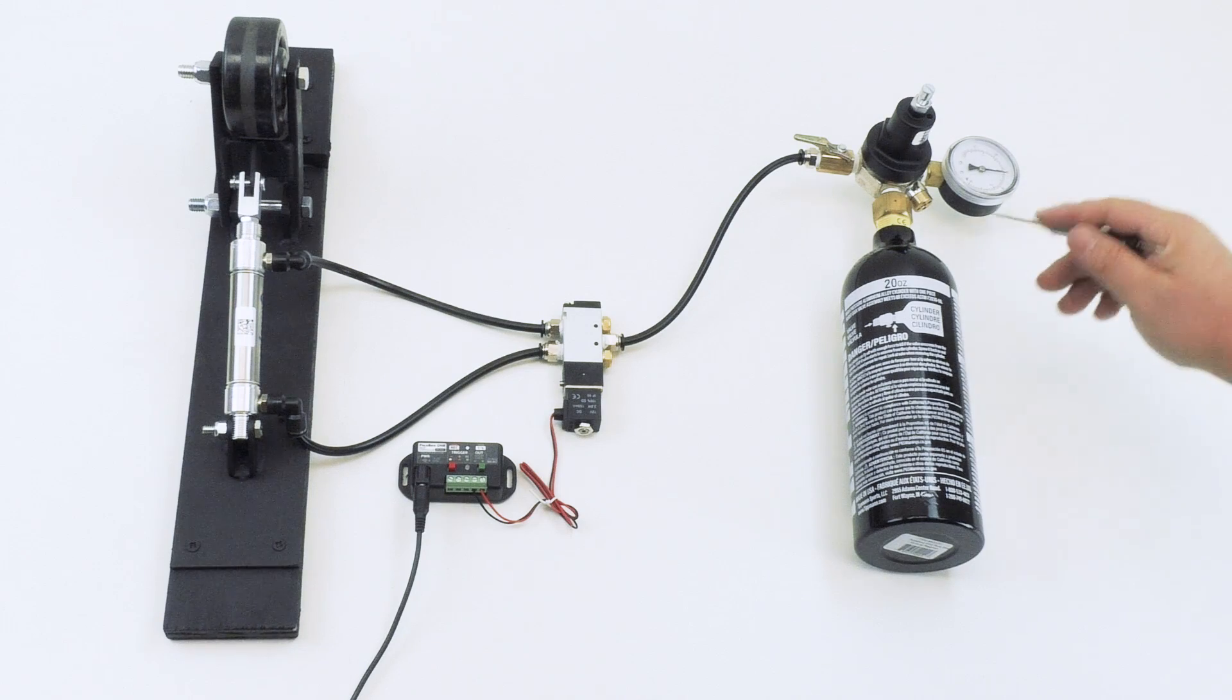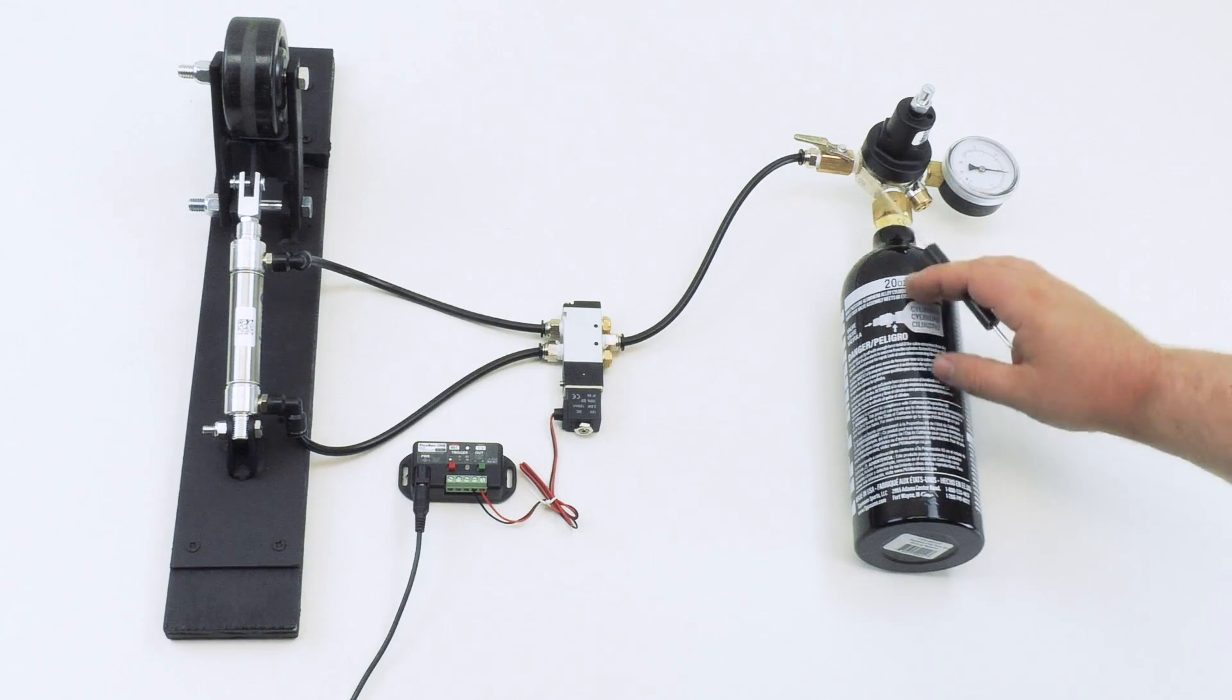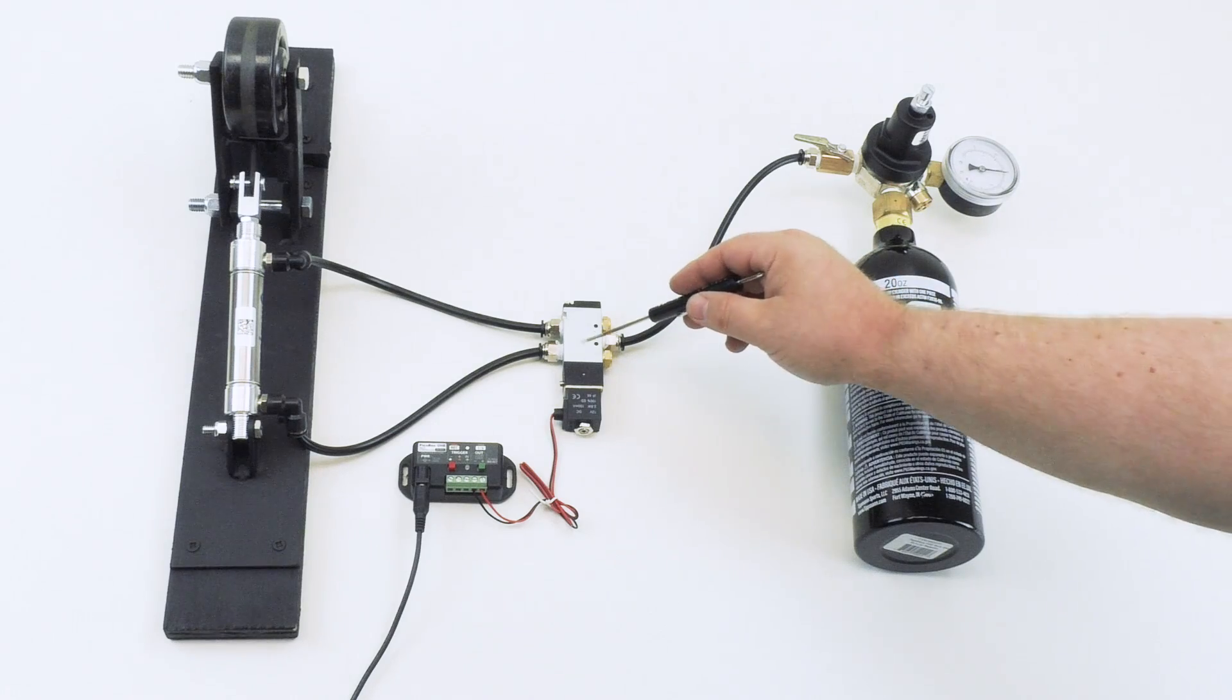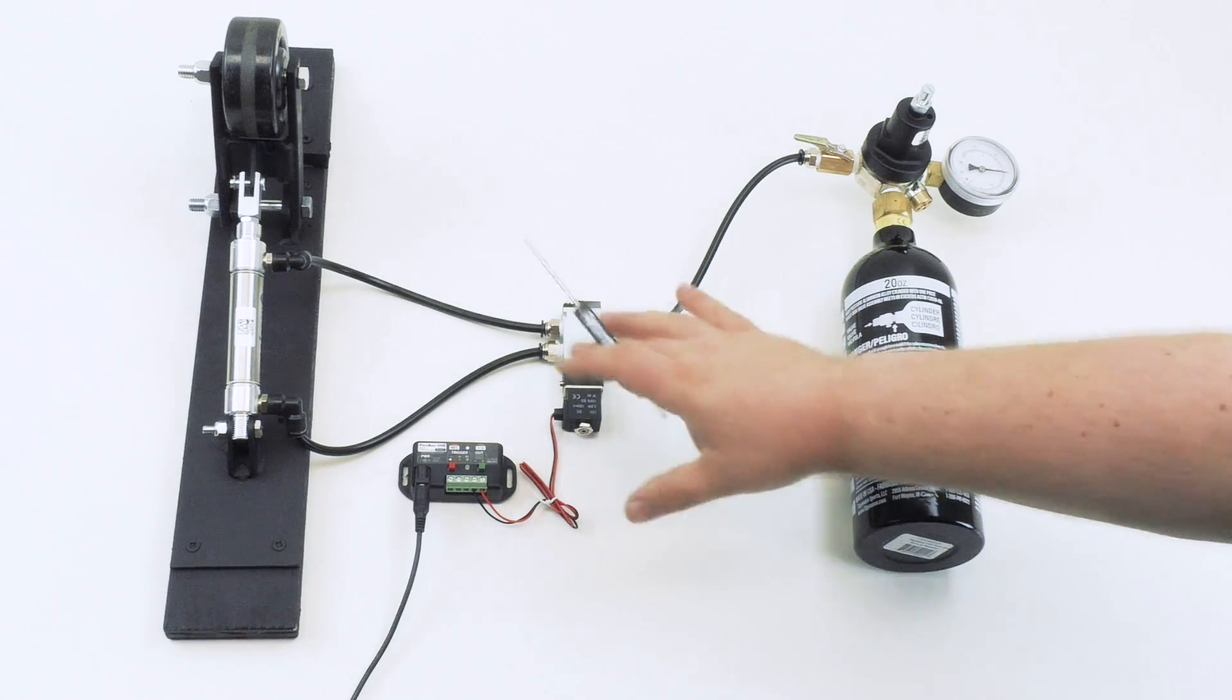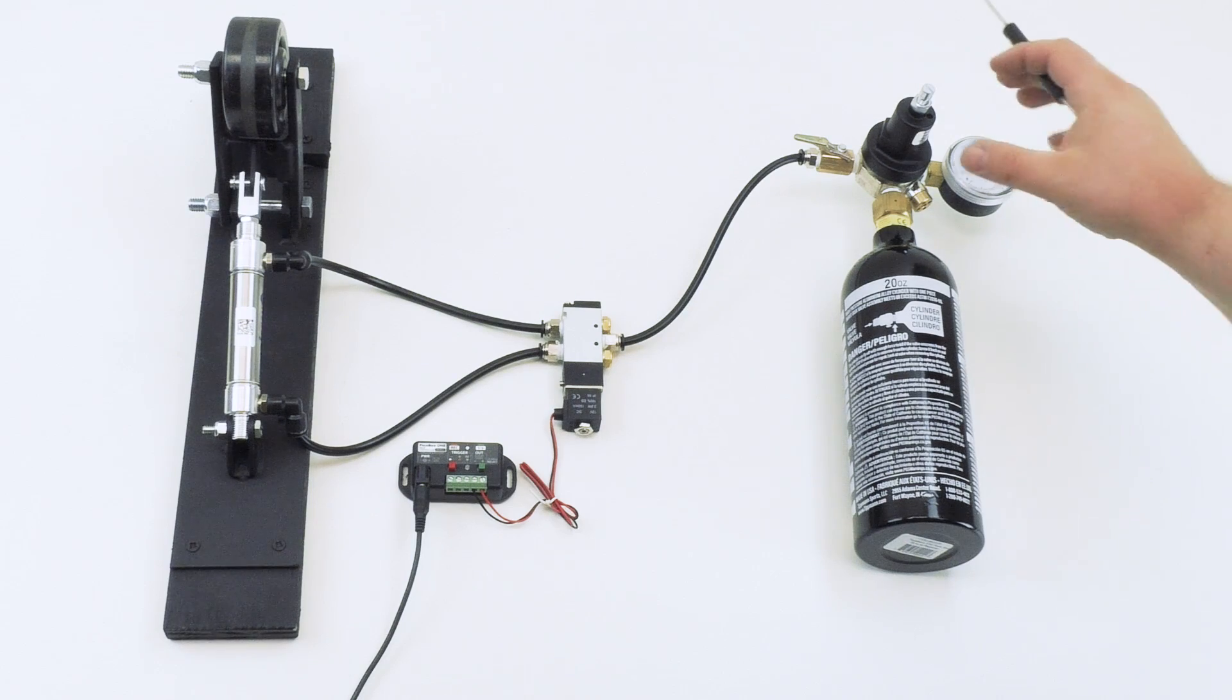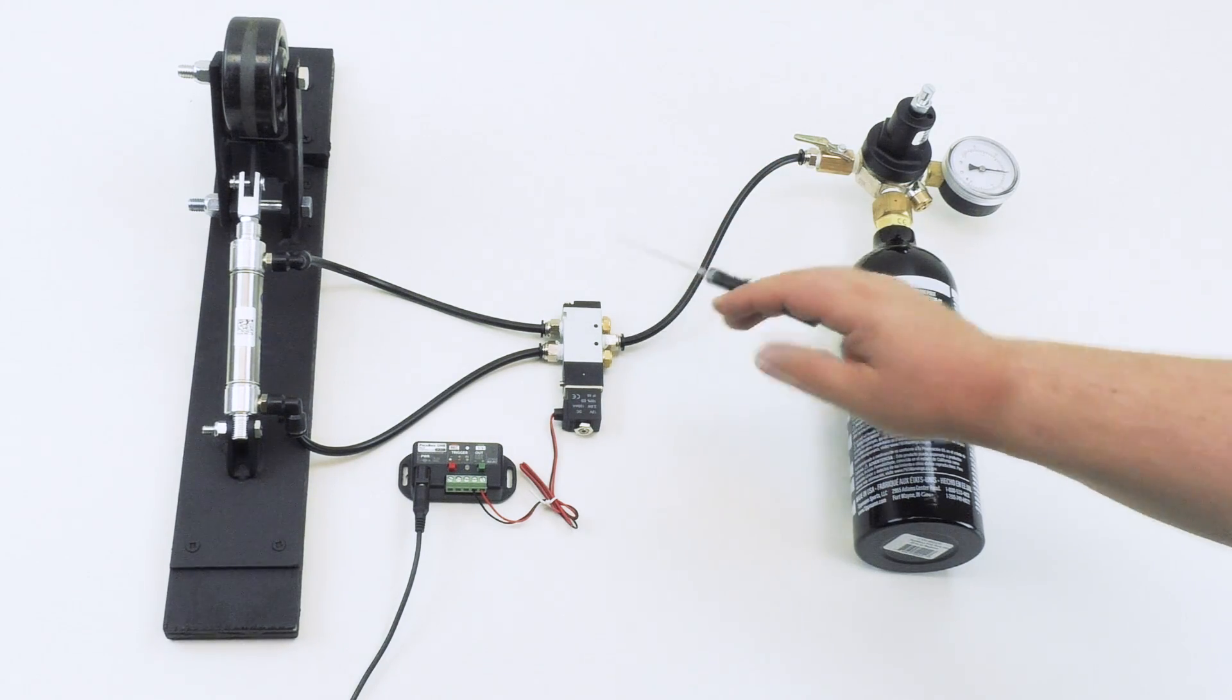So let's take a look at the regulator. This is very important again because this tank is compressed at over 800 PSI. If we were to feed that pressure directly into the valve or the cylinder, it would damage them. They're not rated to handle that high of a PSI. That's why we need a regulator so we can dial down that PSI to something that will work with our pneumatic system.